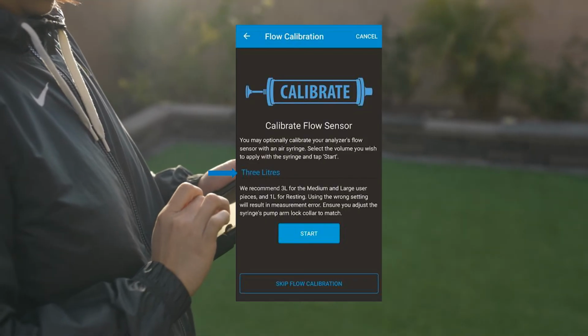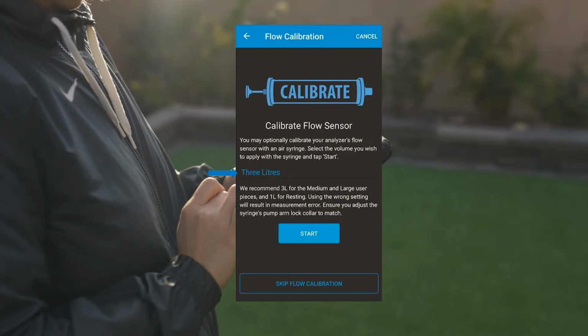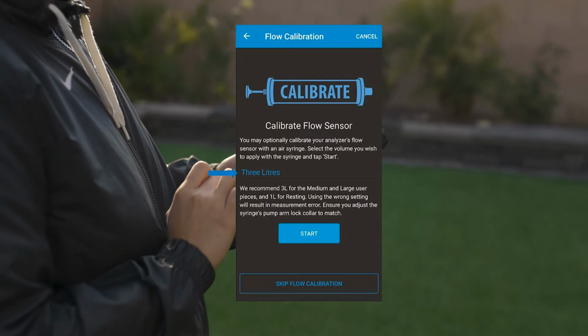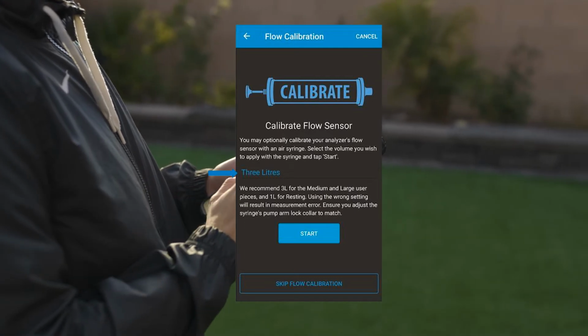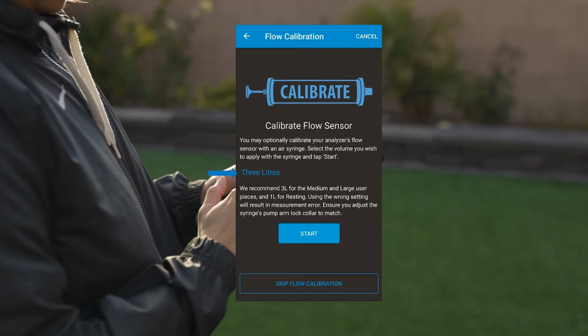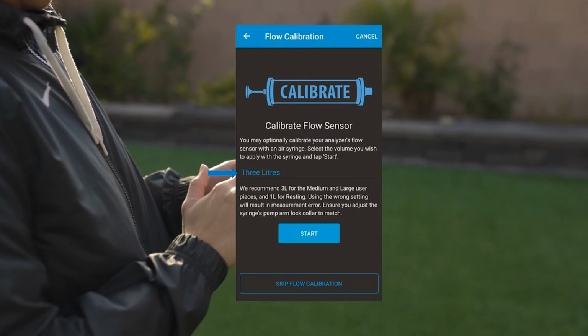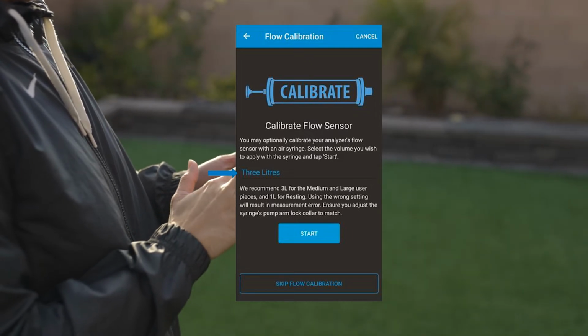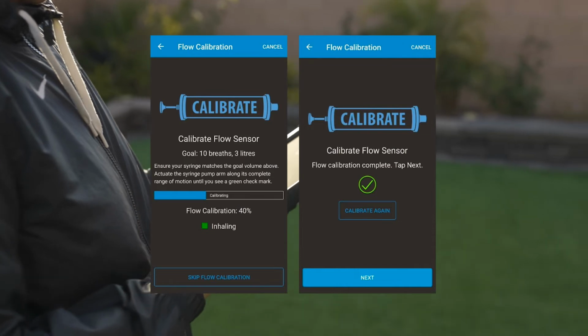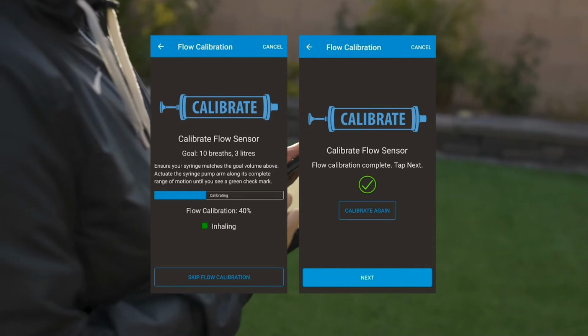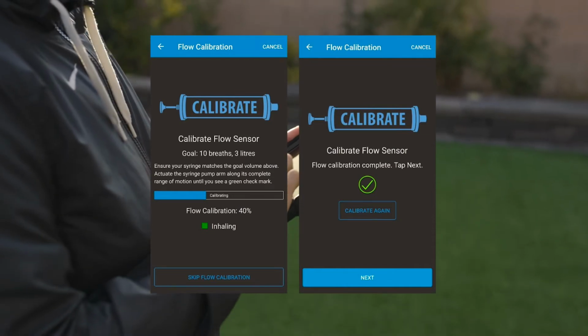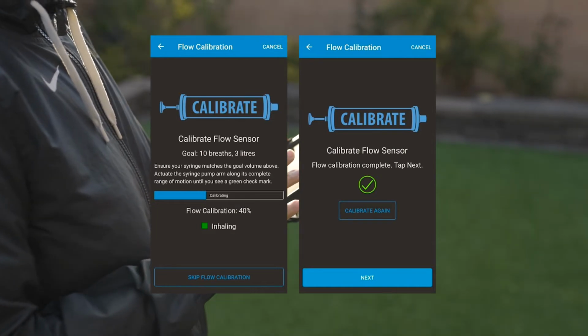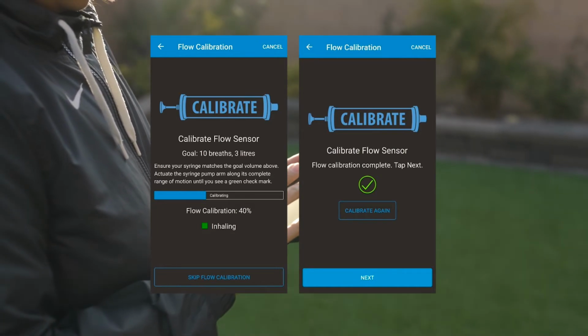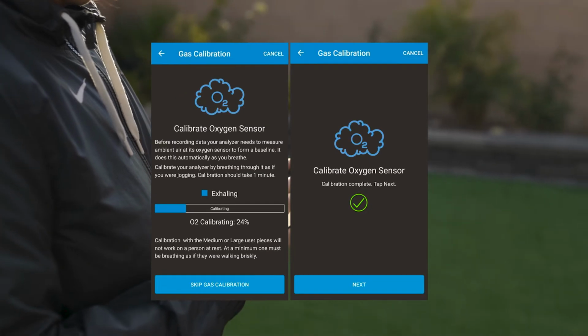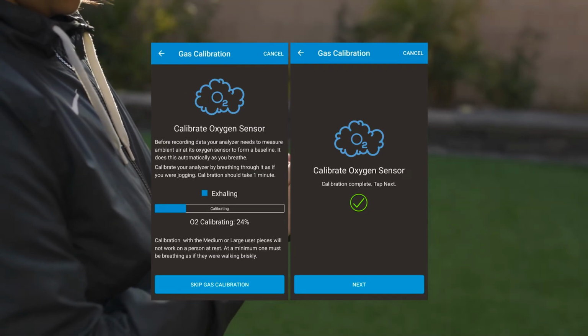The app will ask for the syringe volume being used to calibrate the flow sensor. For the medium and large user pieces, the 3-liter volume is recommended. For the resting user piece, the 1-liter volume is recommended. Calibrating the flow sensor should be done by pumping the syringe at a rate of approximately 20 strokes per minute. The app will show a green check mark once the calibration process is complete. Then tap the next button to proceed to the gas calibration.